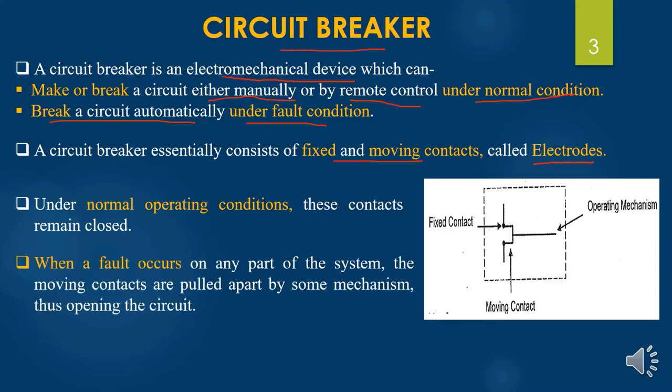But when a fault occurs, the moving contact has a trip coil attached with it. The trip coil gets energized and therefore the moving contact is pulled away from the fixed contact. The two contacts — fixed contact and moving contact — are separated from each other, and the connection between them is broken. Therefore, the faulty current is interrupted from flowing into the circuit.